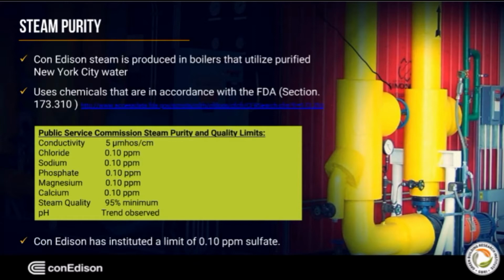Con Edison monitors steam purity by continuously monitoring the steam conductivity in each steam main leaving each power plant. Con Ed reports each incident if there is ever an exceedance on the limits to the New York State Public Service Commission, along with corrective actions that were taken immediately. In addition to the limits prescribed by the PSC, Con Edison has instituted a limit of 0.10 ppm sulfate.